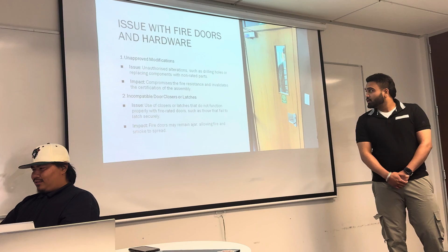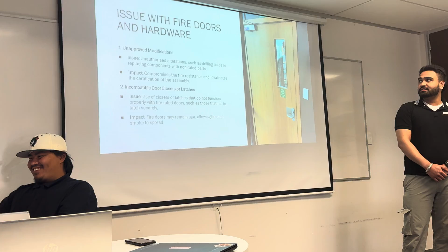The third issue is issues with fire doors and hardware. First, unapproved modification. Mostly, to design the door we do many modifications. What can be the issue? Unauthorized alterations such as drilling holes or replacing components with non-rated parts. The impact: it compromises the fire resistance and invalidates the certification of the assembly. The second one is incompatible door closers or latches. Use of closers and latches that do not function properly with fire rated doors, such as those that fail to latch securely. Impact: fire doors may remain ajar, allowing fire and smoke to spread fast.